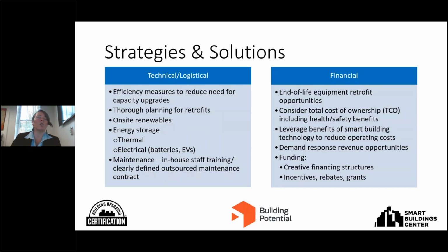Of course, I've mentioned efficiency, it's super important to implement efficiency measures before electrification strategies, reducing your load in the first place. Don't just replace like for like on equipment, don't just look at your nameplate and say this is how much capacity I need. Likely you can reduce your load quite a bit through efficiency measures, and then right-sizing equipment at that point is key to reducing overall cost.